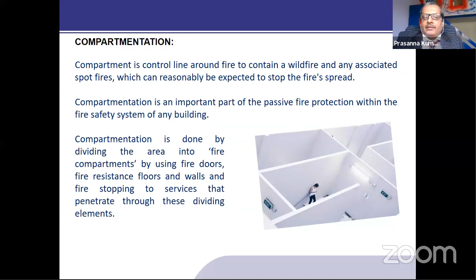So the main objective of the fire compartmentation is to avoid the rapid spread of the fire. It cannot be done when the incident has happened; at that time, the containment cannot be done. It's very difficult to do that. But doing the containment during the design, built within the building, will always help the extinguishing of the fire. As a designer, we look at the compartmentation in three major ways: one is human safety, another is loss prevention, and the third is quicker extinguishment. These are the three parameters for safeguarding the building, the humans and the properties whenever the fire happens.